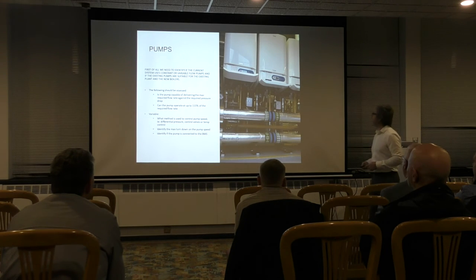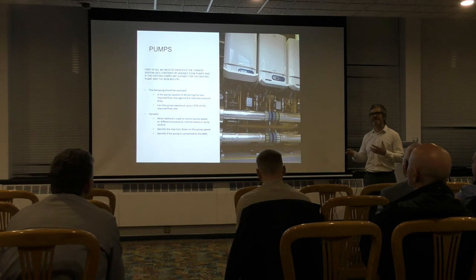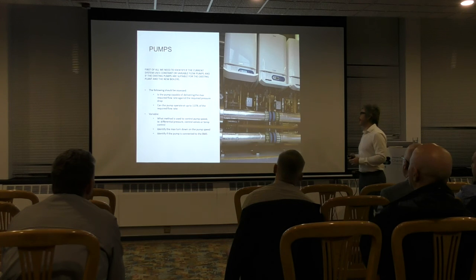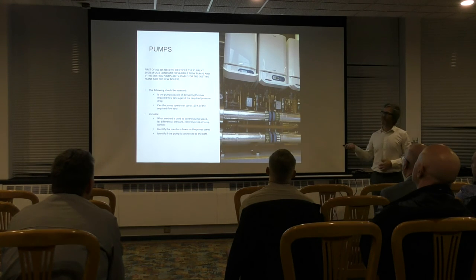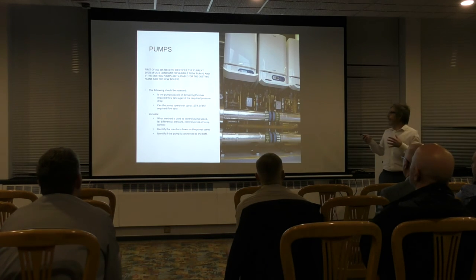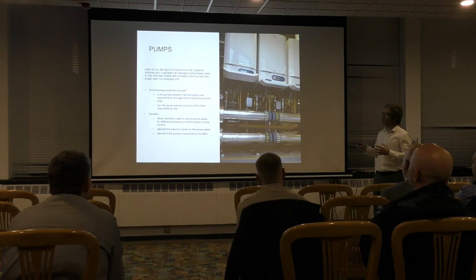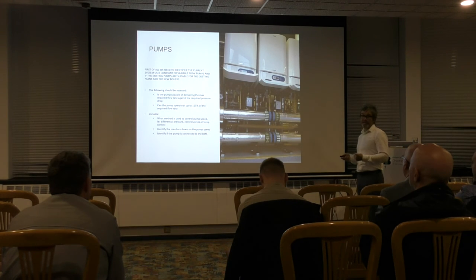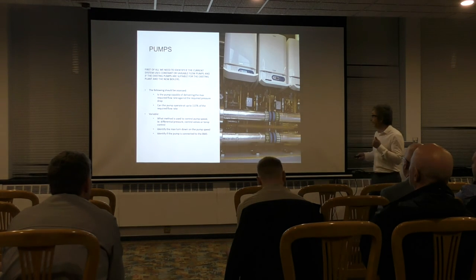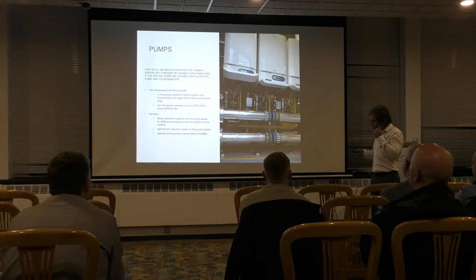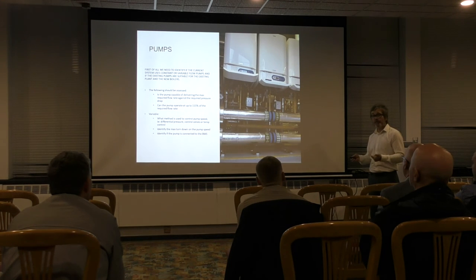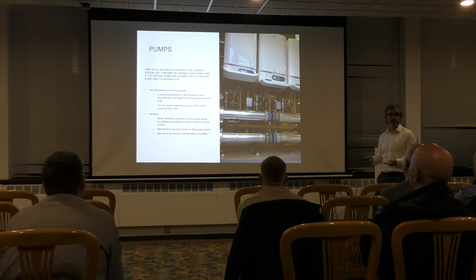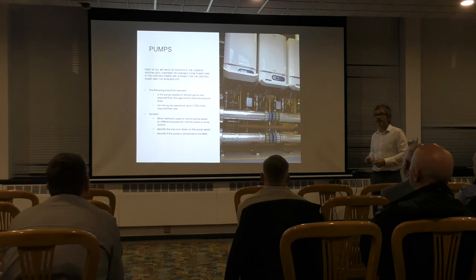The pumps, we kind of touched on pumps really, but I want to say about using existing pumps again. Can we use existing pumps? I mean, two things on the pumps. I would always say, if you are looking at using those existing pumps in that plant, two things: can they overcome the resistance over the heat exchanger, and can they give the required flow rate across that heat exchanger on the new boilers, obviously. If they can do that, then there's no reason why you can't use those pumps.